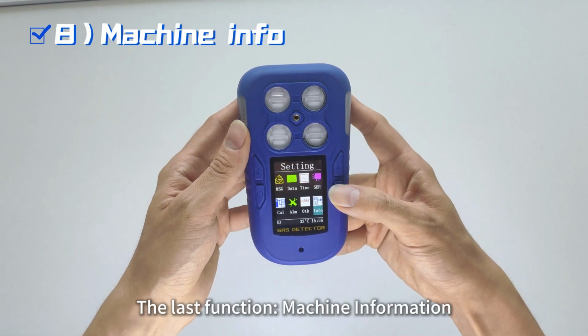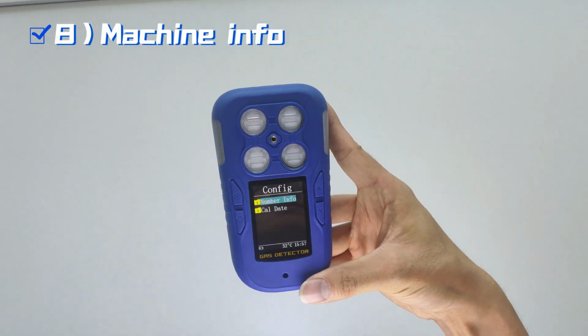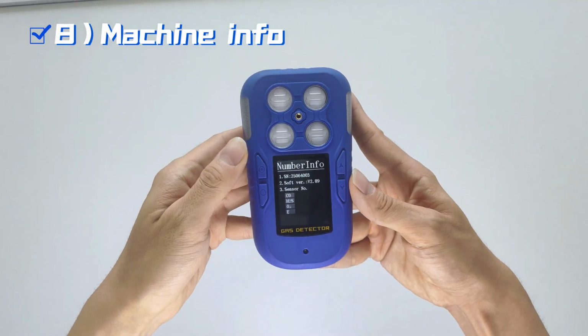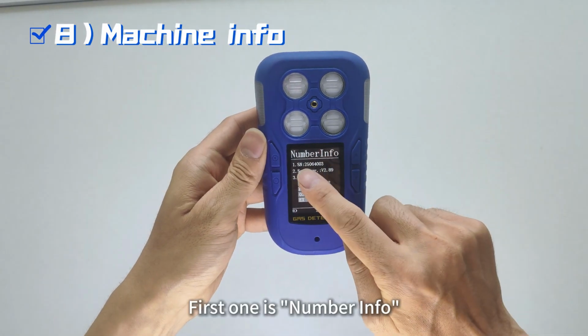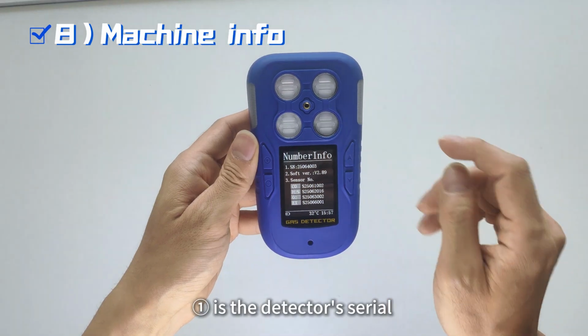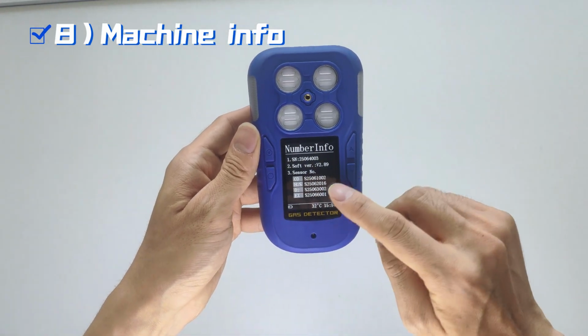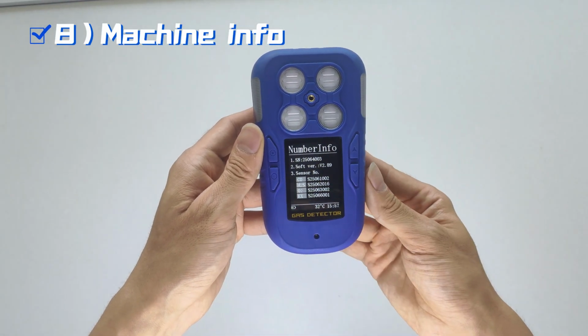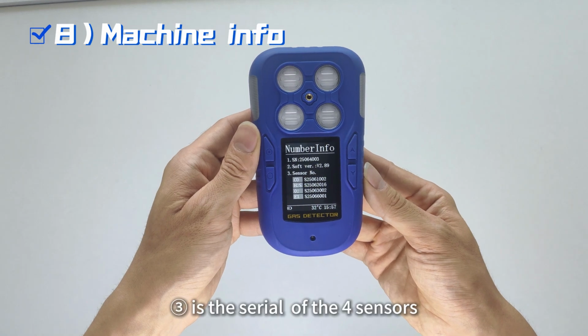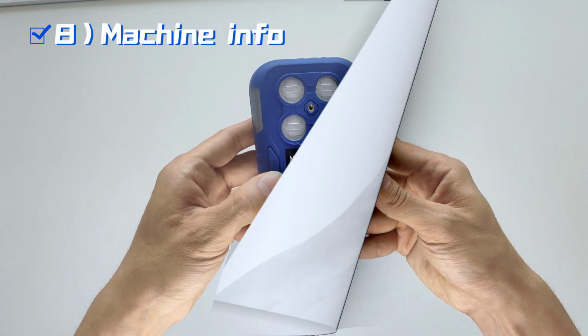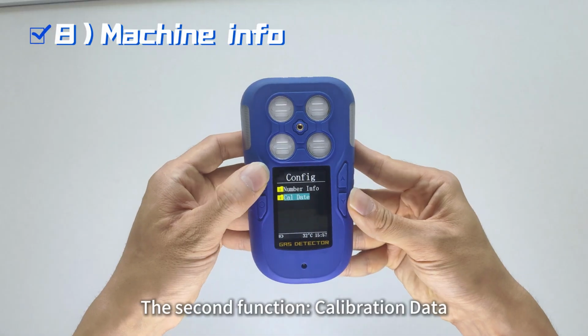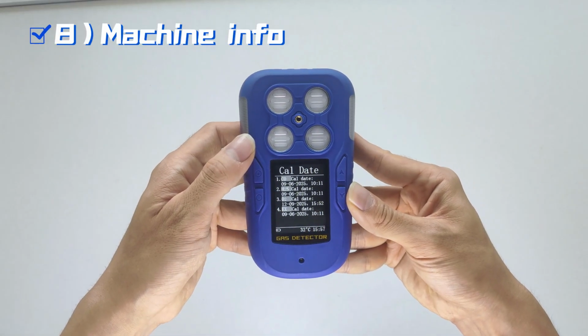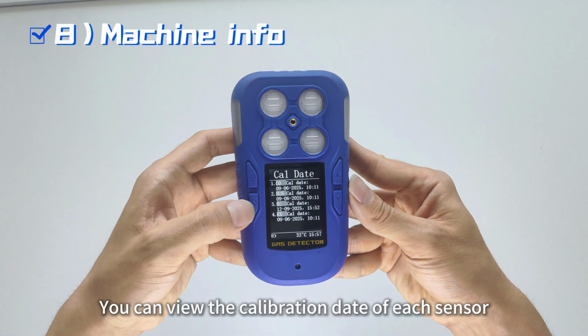The last function, machine information. First one is number info. Number 1 is the detector serial. Number 2 is the software version. Number 3 is the serial of the 4 sensors. The second function, calibration data. You can view the calibration date of each sensor.